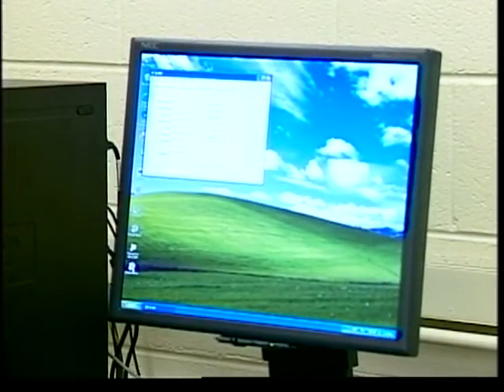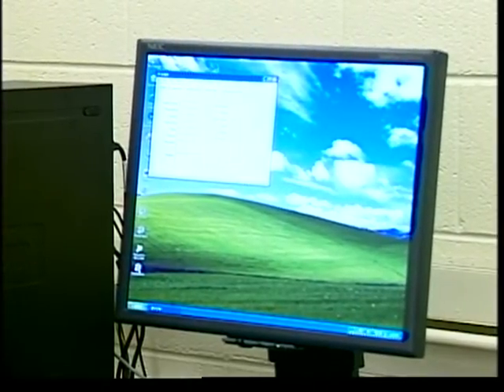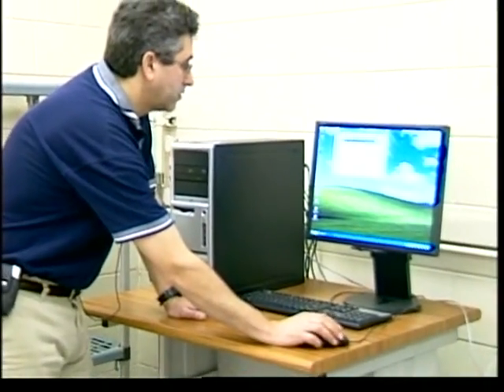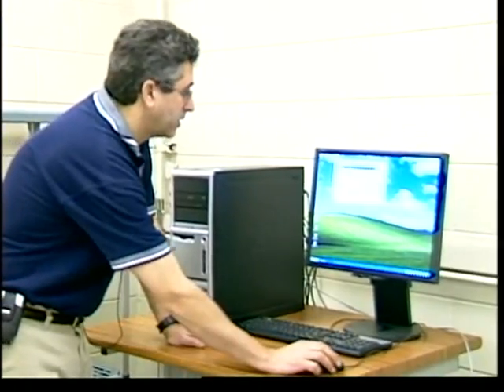What you need to do is load the template file, which was created. The template file has all the specific information for that particular load frame. What I mean by specific information is the calibration factors of the sensors connected to that frame, and also things like step multiplier and properties of the motor that is used. All this information does not change. You don't want to re-enter all the information every time. So what you do is load the template file. You must load a template file before you run your test. So this is blank. I'm going to load a template file. I go to File and Load, and there's a template file that we created here for you.